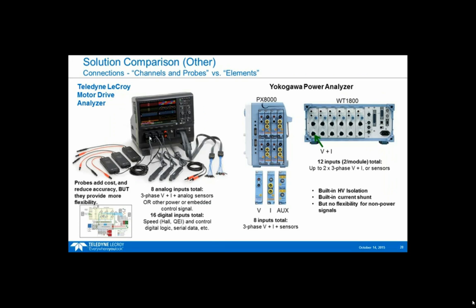I have the ability to utilize this channel any way I want for current or voltage and look anywhere in my circuit here. Plus, I have digital logic inputs too if the product's configured with the MSO. A power analyzer has direct inputs. Looks something like this. These are two different versions here, but the concept is the same. There's banana jack inputs for voltage. There's a BNC and perhaps lugs to feed in your current signal.